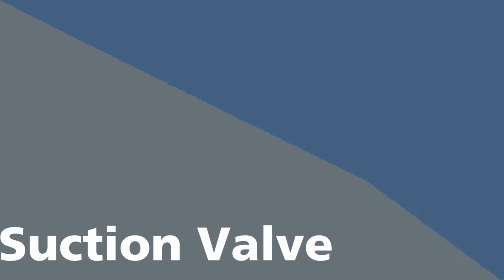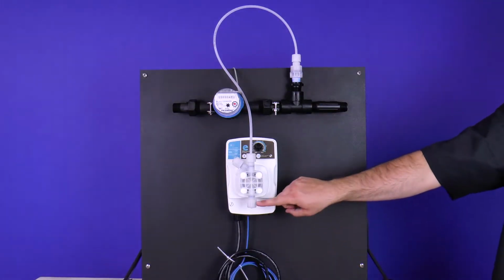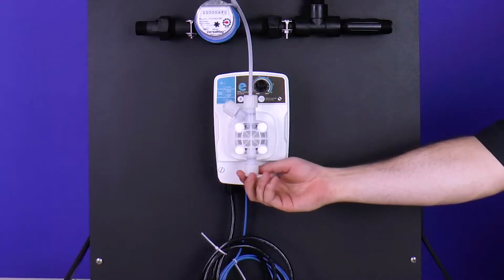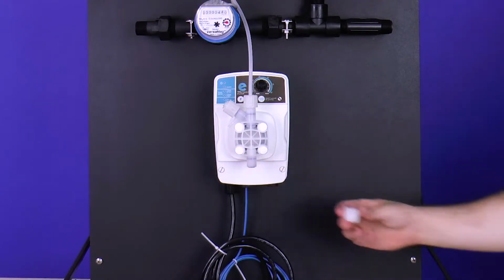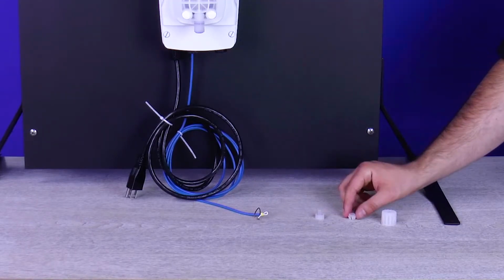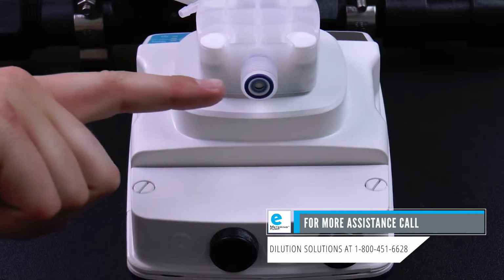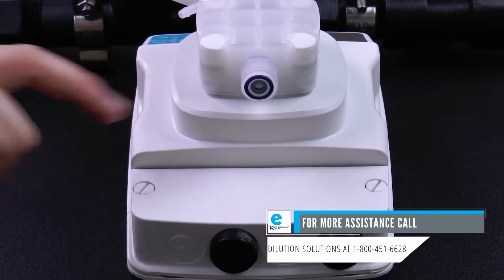Suction valve. Rebuild the suction valve by locating the suction valve at the bottom of the pump head and remove the tube nut, collar, and nozzle. Set the connections aside and make sure not to lose them. Make sure not to lose the blue O-ring directly at the bottom of the suction valve.